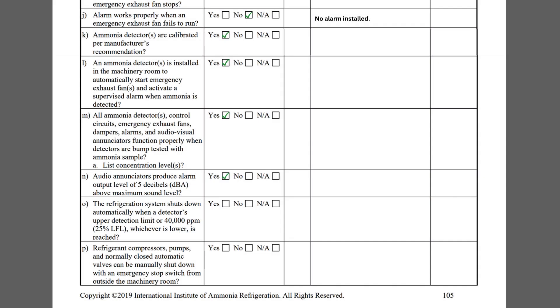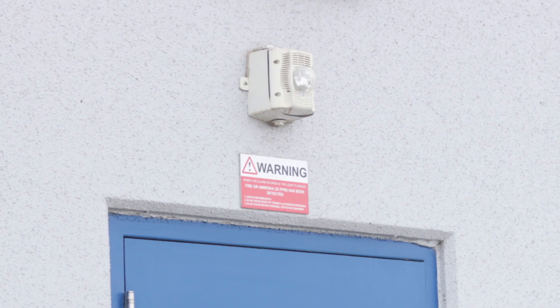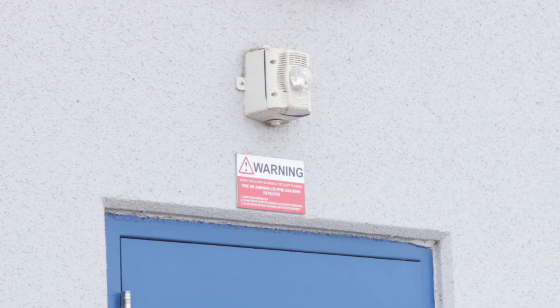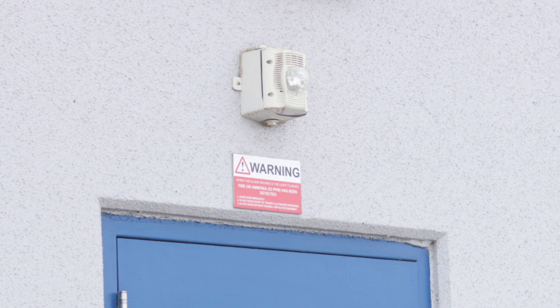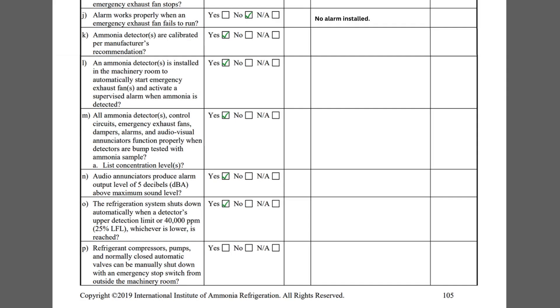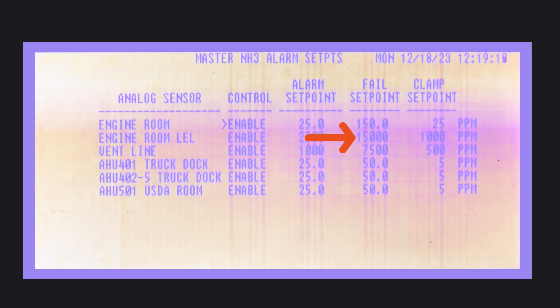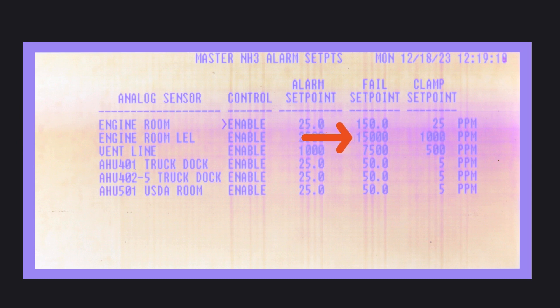Item N asks if the audio annunciators produce alarm output levels of 5 dB above the maximum sound level. These ammonia alarms provide a sound level well exceeding this requirement. Checklist Item O asks if the refrigeration system shuts down automatically when a detector's upper detection limit of 40,000 ppm is reached. The PLC HMI indicates that the shutdown set point is 15,000 ppm.